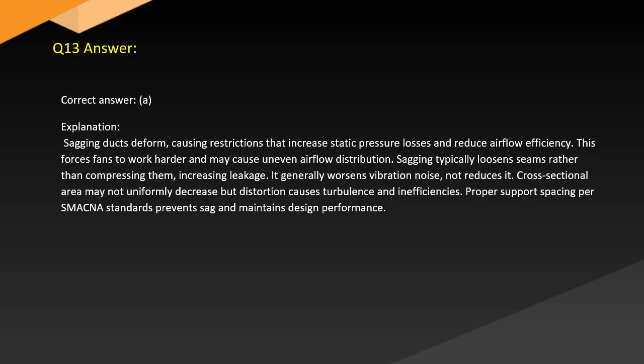Answer. Correct answer: A. Explanation. Sagging ducts deform, causing restrictions that increase static pressure losses and reduce airflow efficiency. This forces fans to work harder and may cause uneven airflow distribution. Sagging typically loosens seams rather than compressing them, increasing leakage. It generally worsens vibration noise, not reduces it. Cross-sectional area may not uniformly decrease, but distortion causes turbulence and inefficiencies. Hanger spacing per SMACNA standards prevents sag and maintains design performance.